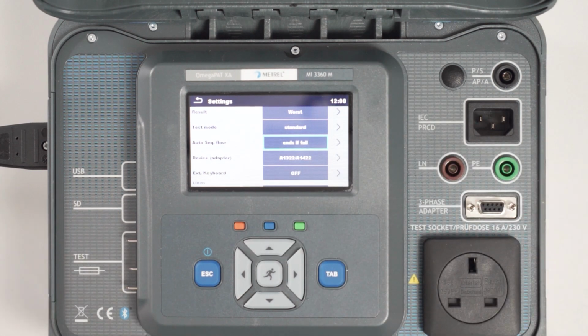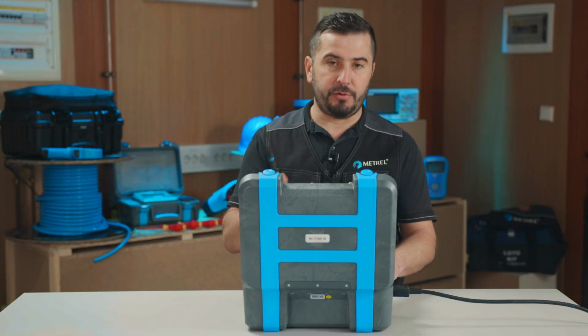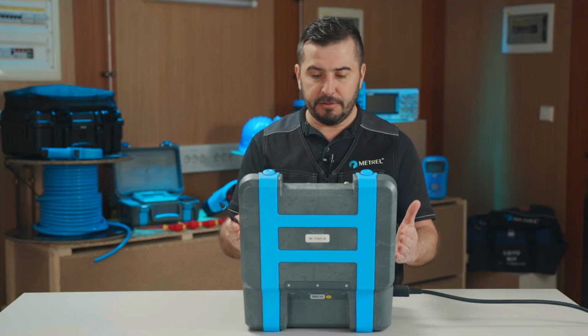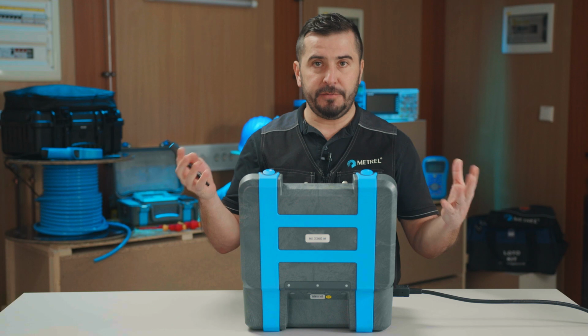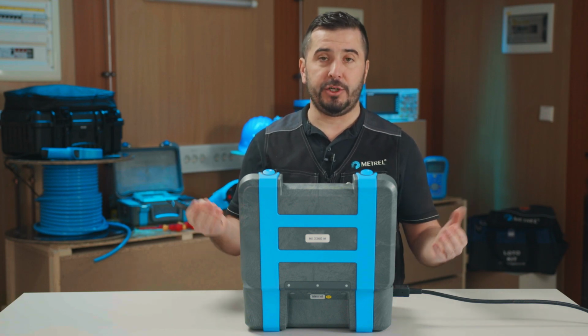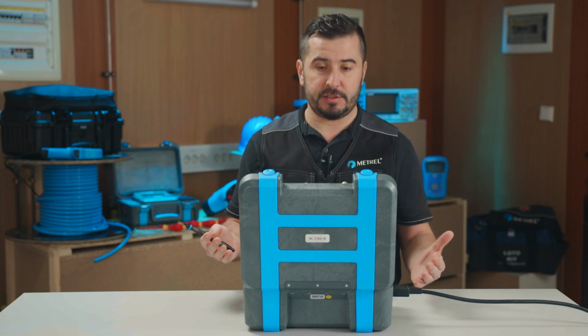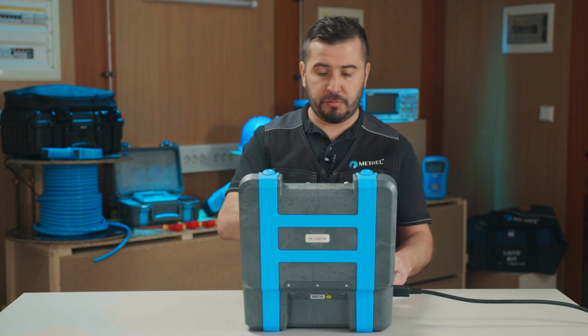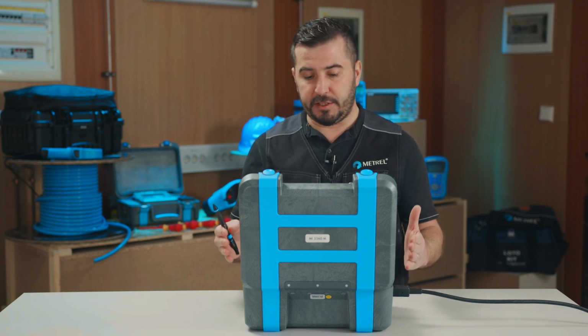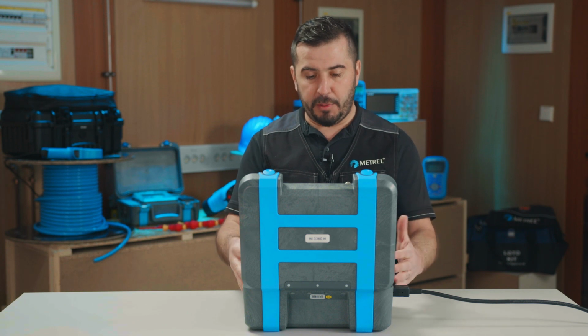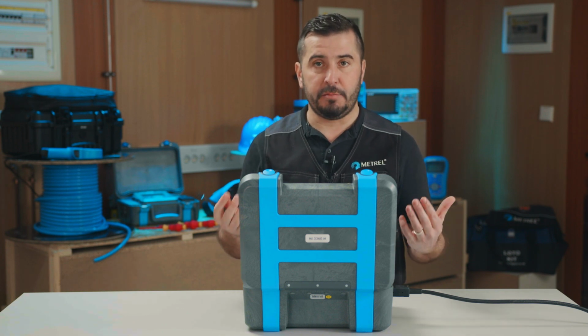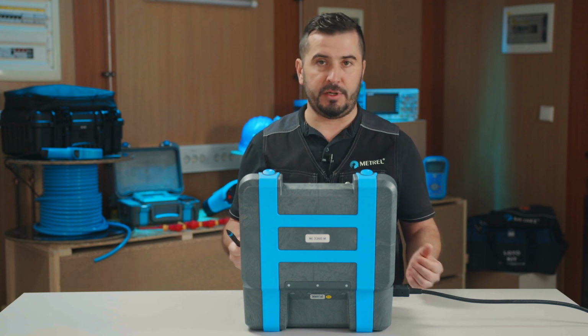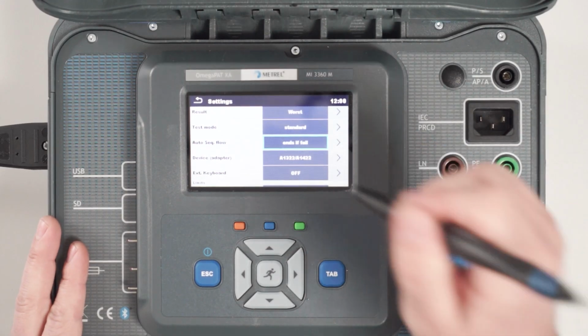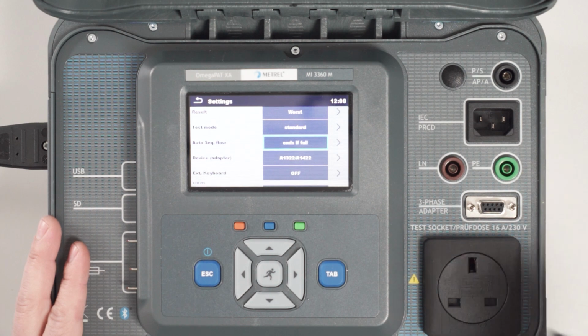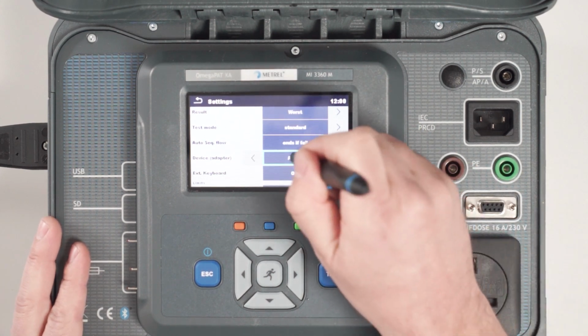We have also the option here to connect different adapters. For example, we can connect to this single-phase appliance tester, three-phase active appliance tester. We actually have two three-phase active appliance testers, which can be connected to this instrument, and then our appliance tester Omega serves as a master unit and controls the other one. So the option is to also test all sorts of three-phase equipment.